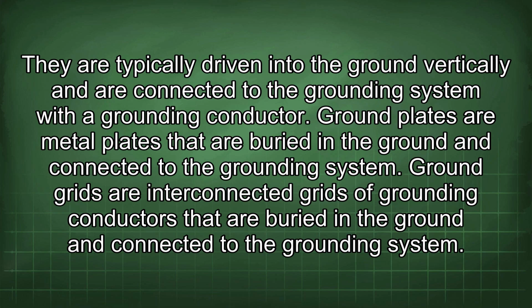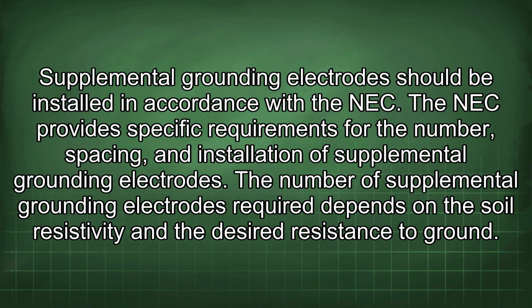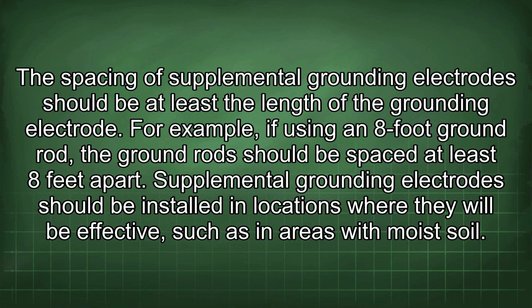Ground plates are metal plates that are buried in the ground and connected to the grounding system. Ground grids are interconnected grids of grounding conductors that are buried in the ground and connected to the grounding system. Supplemental grounding electrodes should be installed in accordance with the NEC. The NEC provides specific requirements for the number, spacing, and installation of supplemental grounding electrodes. The number of supplemental grounding electrodes required depends on the soil resistivity and the desired resistance to ground. The spacing of supplemental grounding electrodes should be at least the length of the grounding electrode. For example, if using an 8-foot ground rod, the ground rods should be spaced at least 8 feet apart.